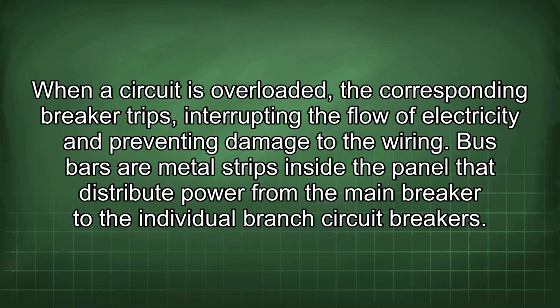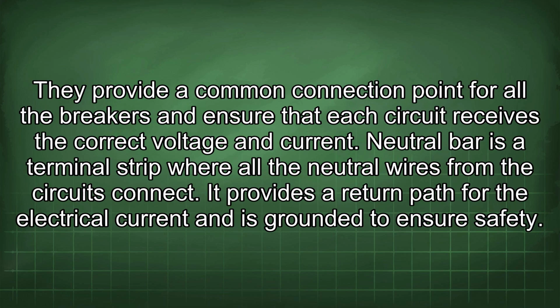Bus bars are metal strips inside the panel that distribute power from the main breaker to the individual branch circuit breakers. They provide a common connection point for all the breakers and ensure that each circuit receives the correct voltage and current. The neutral bar is a terminal strip where all the neutral wires from the circuits connect. It provides a return path for the electrical current and is grounded to ensure safety.